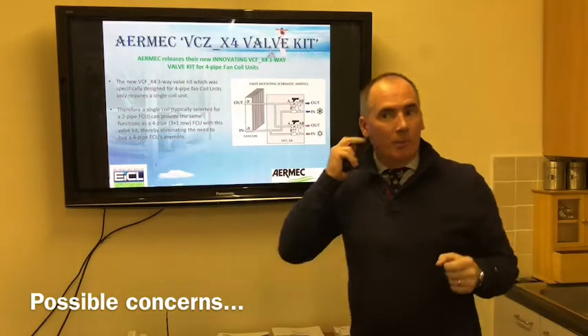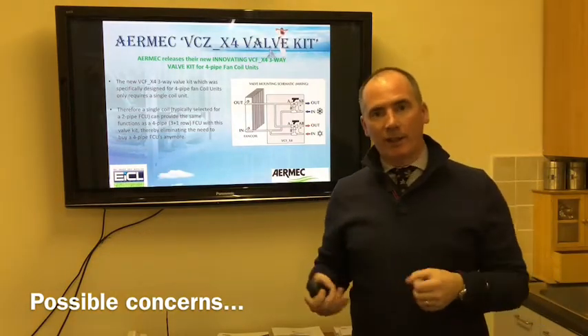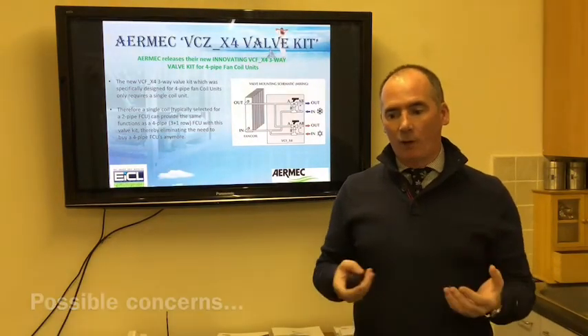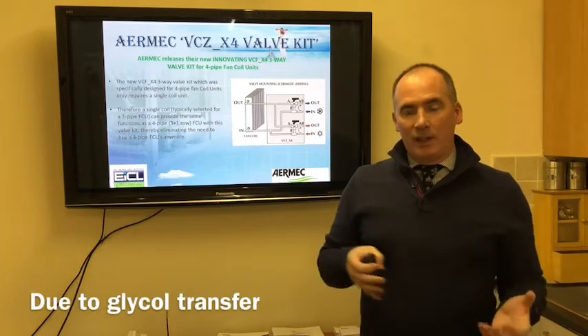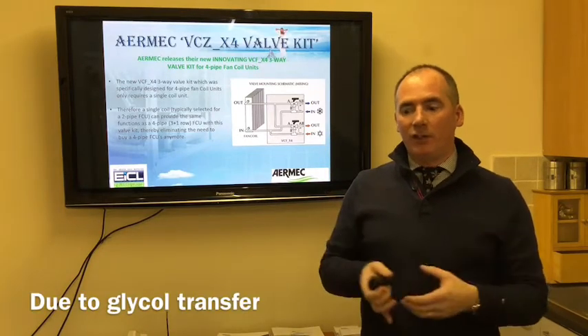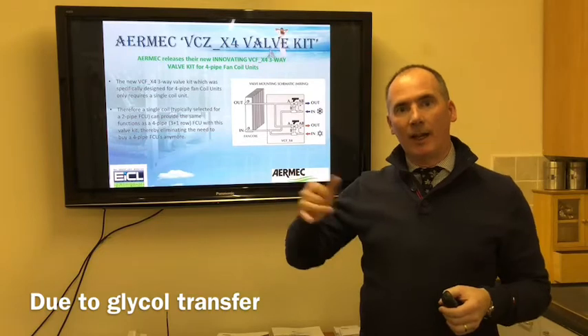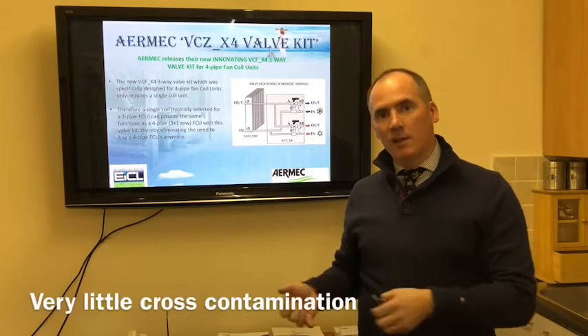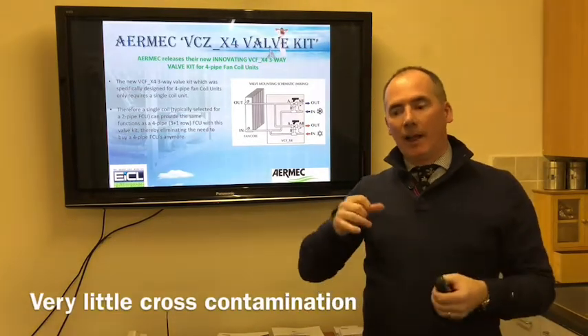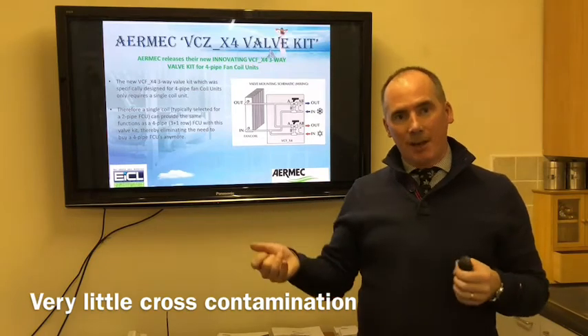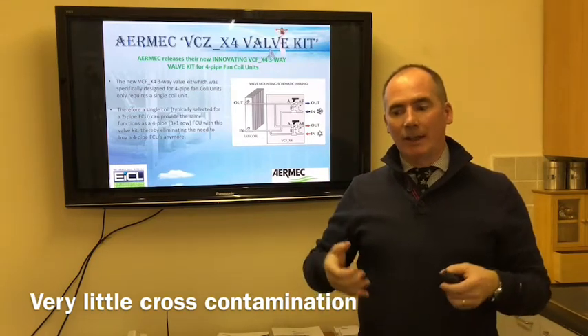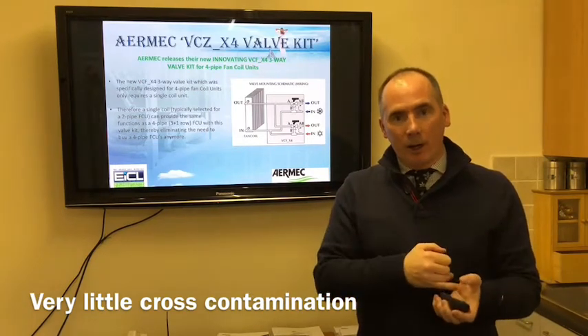I know some consulting engineers are looking at this. We've promoted this over the last number of years. There was a little bit of resistance, the reason being there can be some glycol change if you have glycol in your chill water system and not in your heating system. Of course you can have a certain amount of contamination between one side and the other. So you do need to be aware of that.